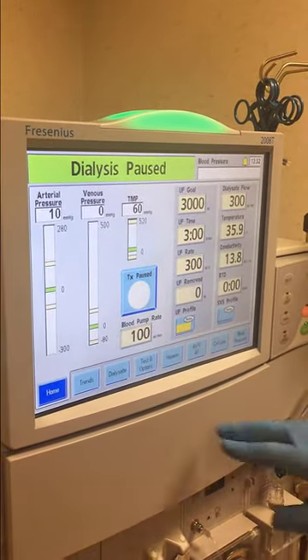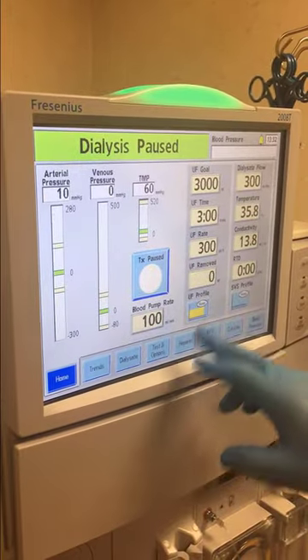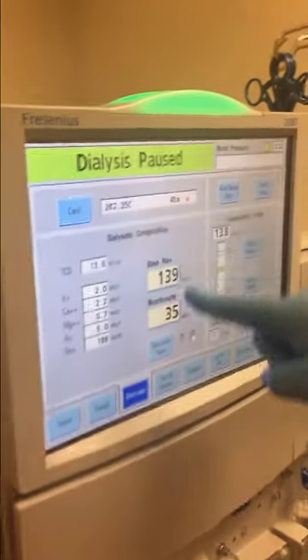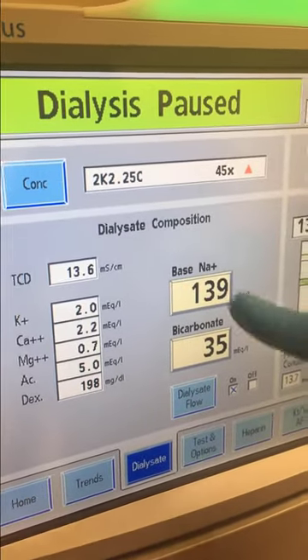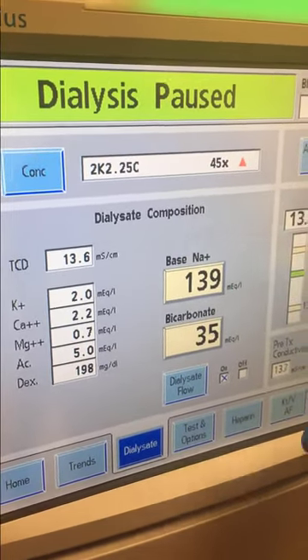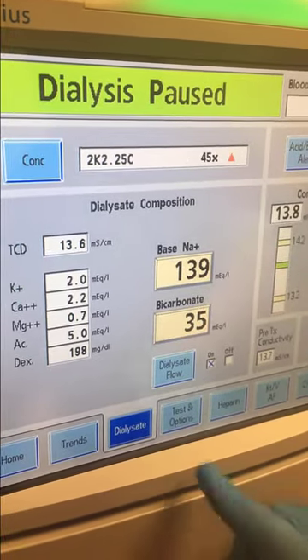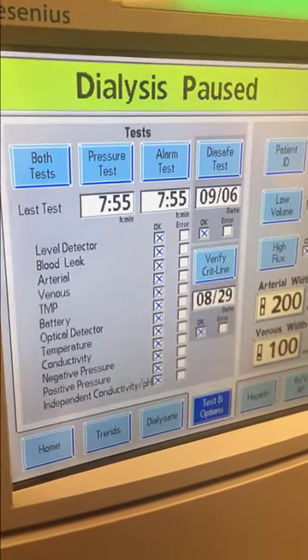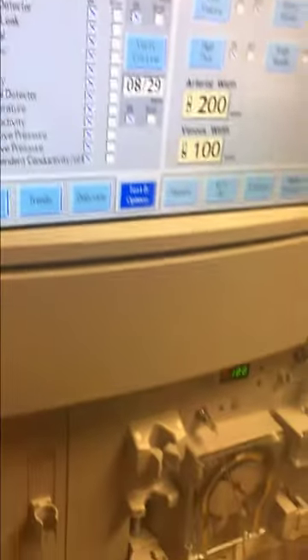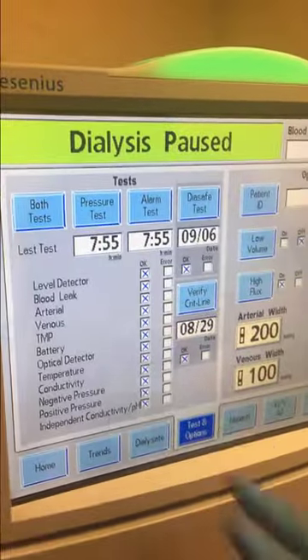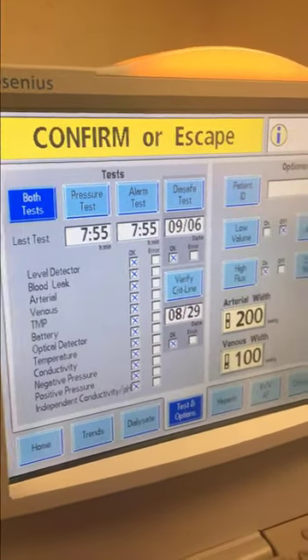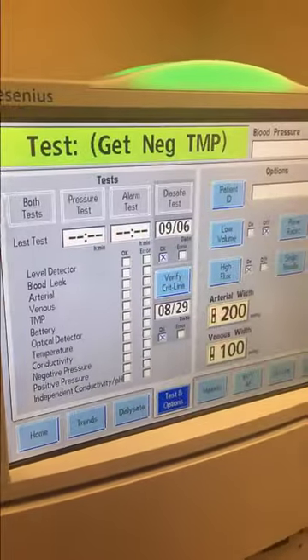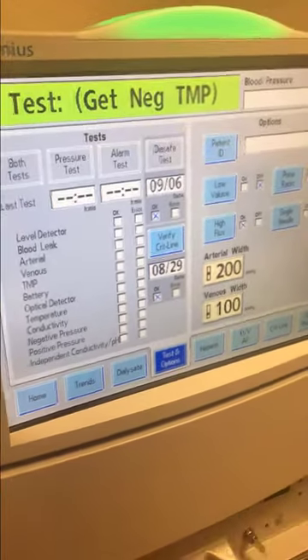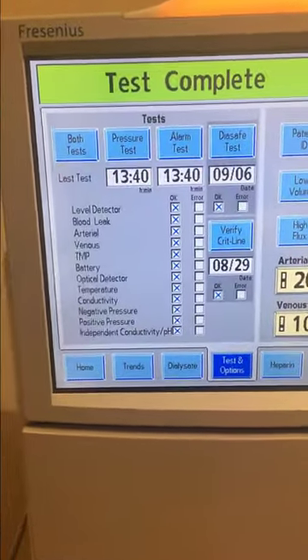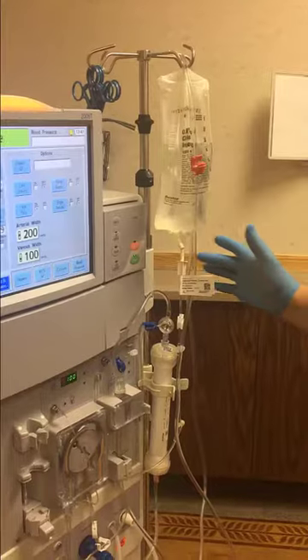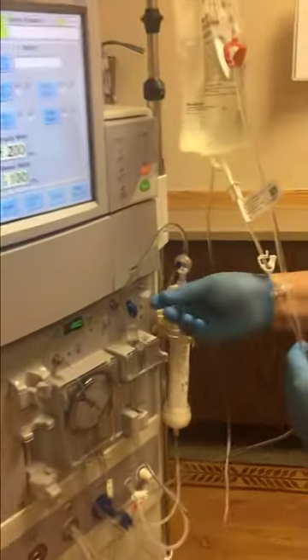He is pointing out that if the machine is not green, the bar across the top, like if the conductivity isn't in normal range, the machine will not go into test. So he's going to select tests and options, and he's going to select both tests and then confirm. There are two rows on that screen. One row says OK. The second row says error. So we need to have an error-free test. So we had all selected OK.